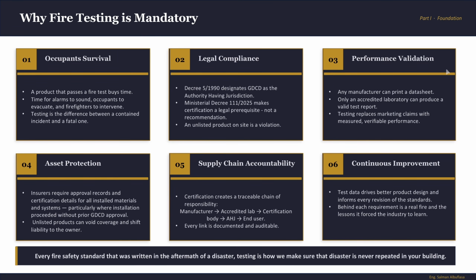Performance validation. Any manufacturer can print a datasheet. I can do one right now from Canva. I can put any number I want on it. There's nothing stopping me. But only an accredited laboratory can produce a valid test report: independently audited, verified results that are traceable, and can produce a valid fire testing report. See, a datasheet tells you what a manufacturer wants you to believe about their product, but a fire test tells you exactly what happened when exposed to fire according to the testing criteria, and these two are not the same documents.